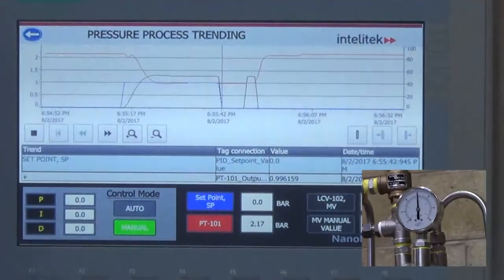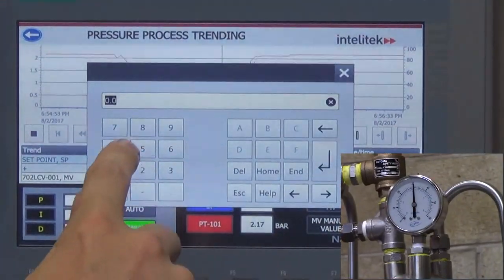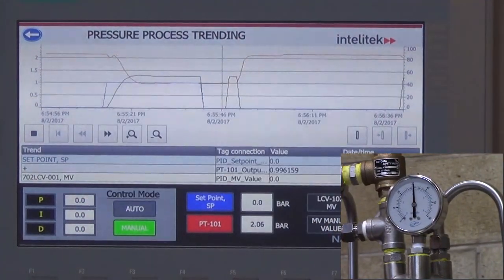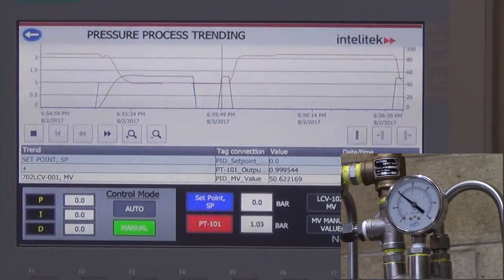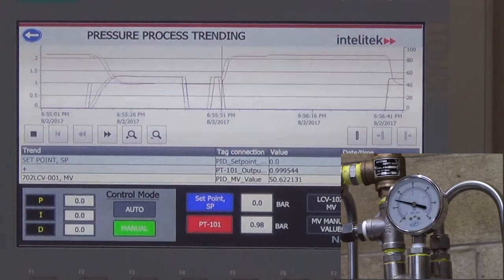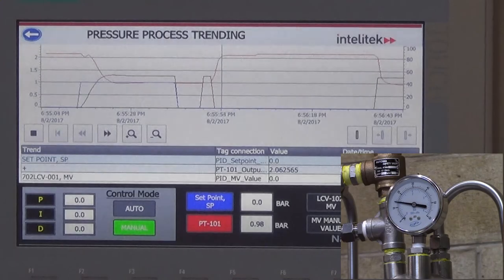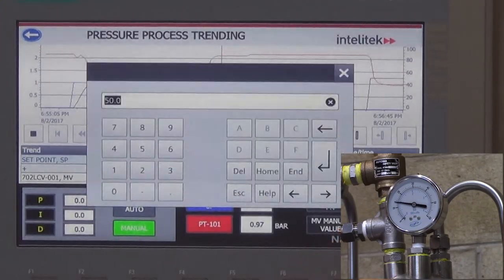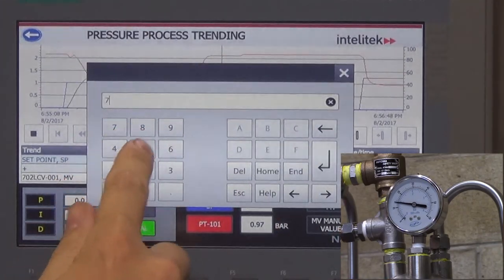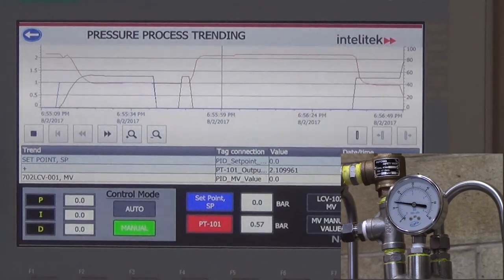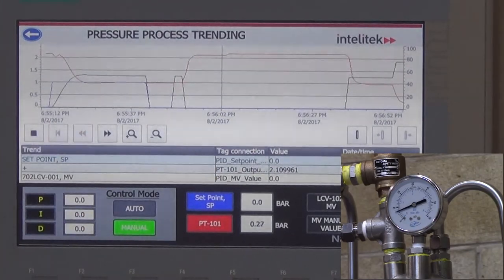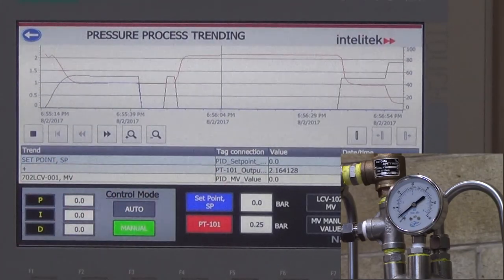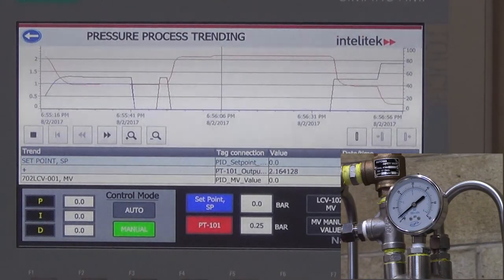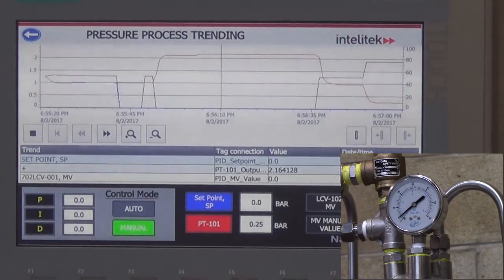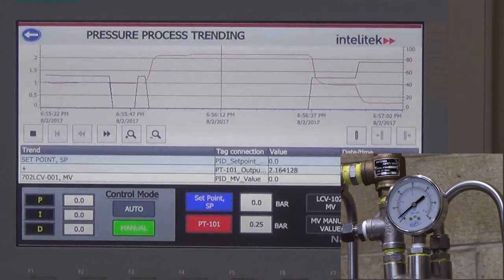So, like before, I can manually control the valve to make it lose air up to a certain point or completely empty the tank. So I can, you know, if I open the valve up 75%, we get down to a quarter bar of air pressure, which is the unit we're taking our measurements in. It's also the unit the sensor natively gives feedback in.